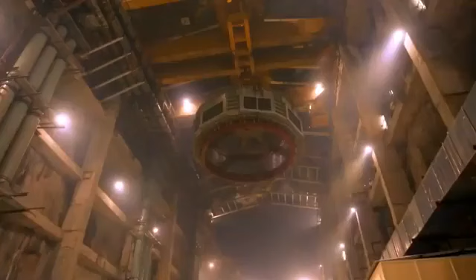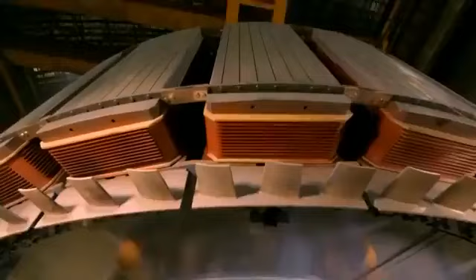During the high voltage test, one of the bars failed. So we replaced the bar and put the machine in the dryout. We lowered the stator day before yesterday, and today we're planning to lower the rotor.